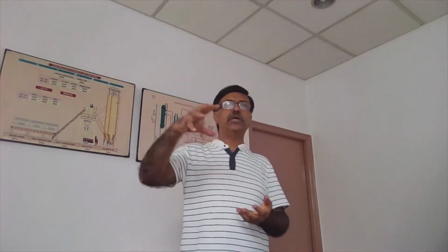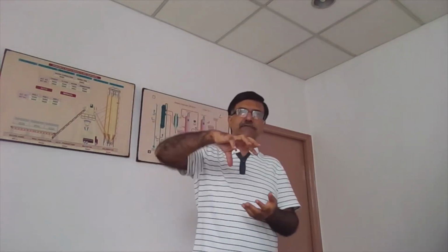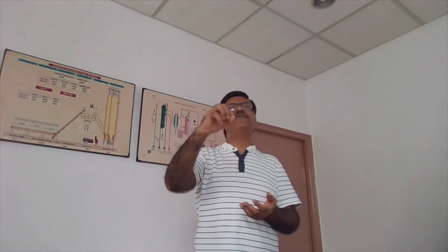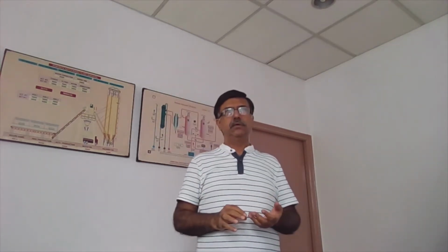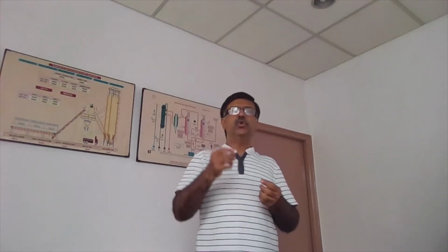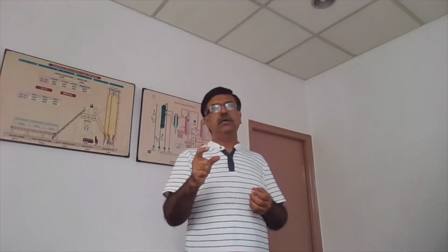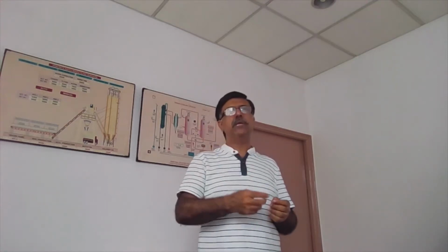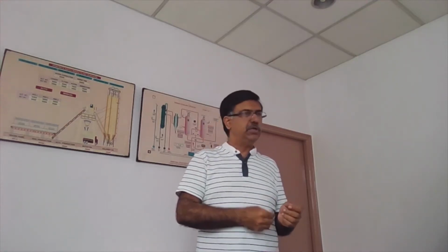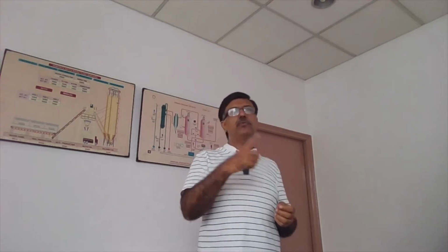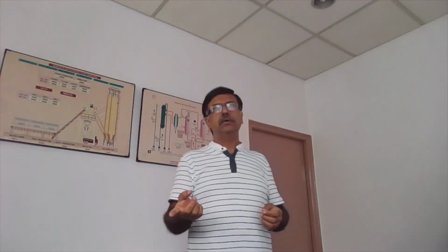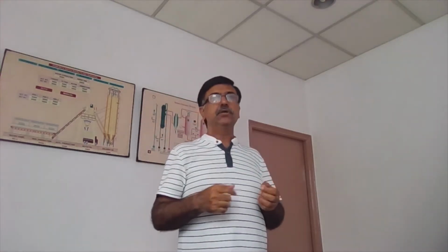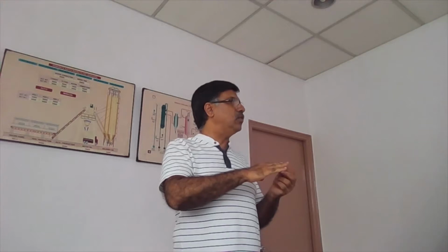For example, in Asian Paints, they want a valve for that color making, they want it to open to 65%. How do you achieve that 65%? So you give an analog output command. So analog output command could be 4 to 20 milliampere, 0 to 20 milliampere, 0 to 10 volts, minus 5 to plus 5, minus 10 to plus 10, and it is continuously changing, right? So anything, any value that can change.